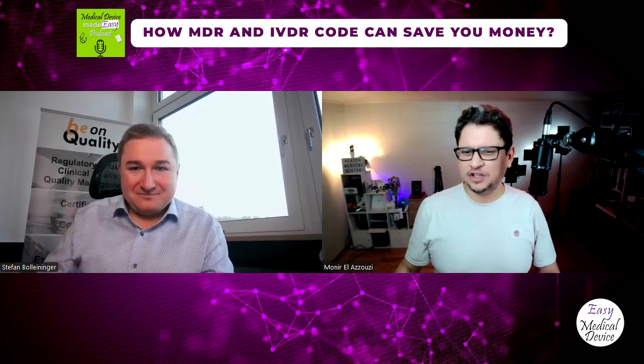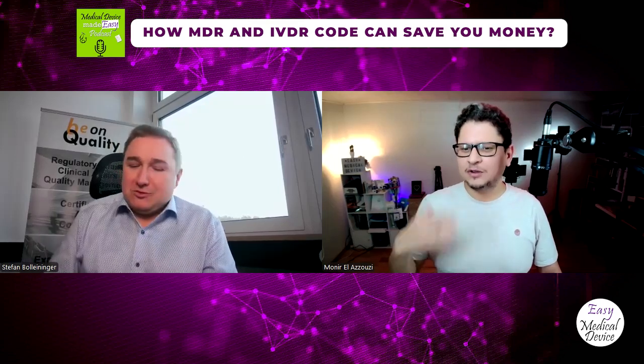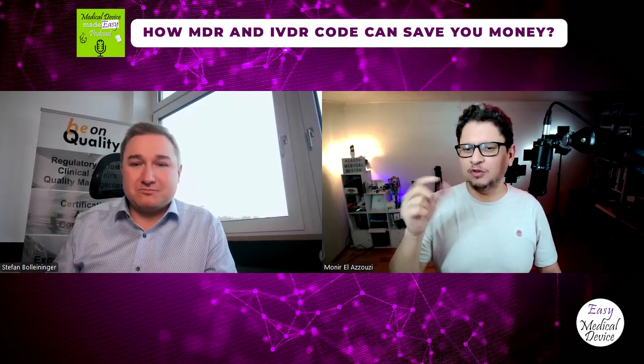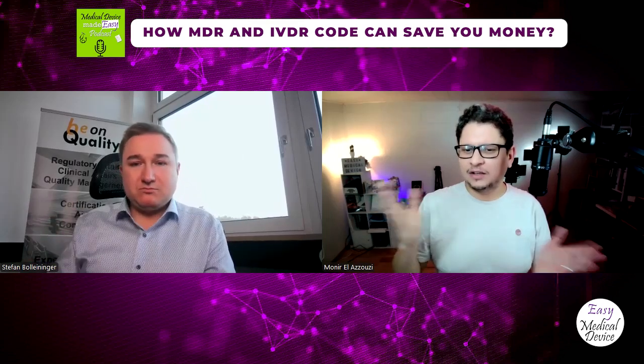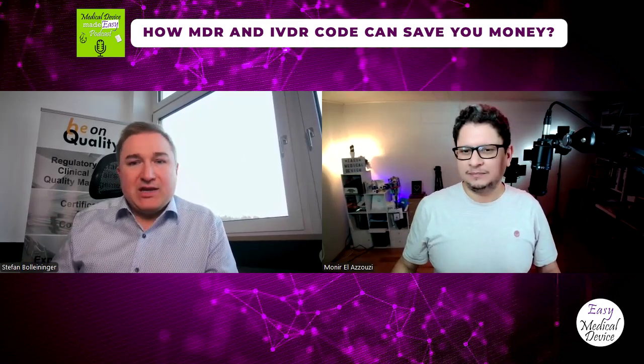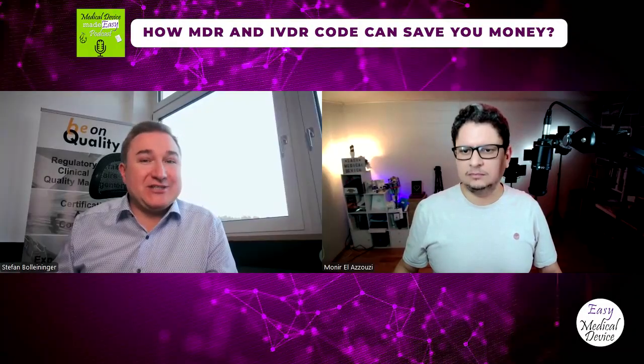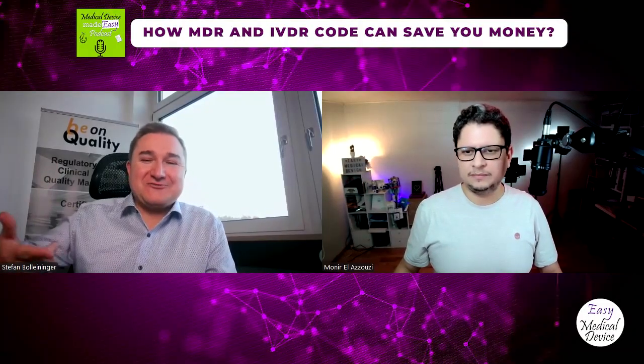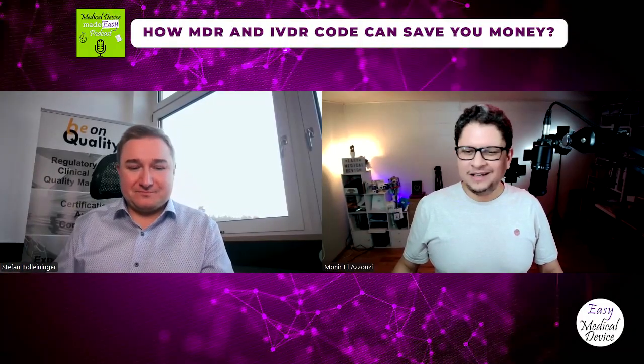Exactly. Just with the same code, with the same things, because usually we are just adding some functionality, but it's not a different intended purpose. It's the same intended purpose, the same code, the same thing. So yeah, same MDN, same MDA, same EMDN. Then you can put it on the list of your products as an update or as a new product, and then tell the notified body, here it is, and they will not look into that until your certification time is done. So exactly, the next certification round. Exactly.